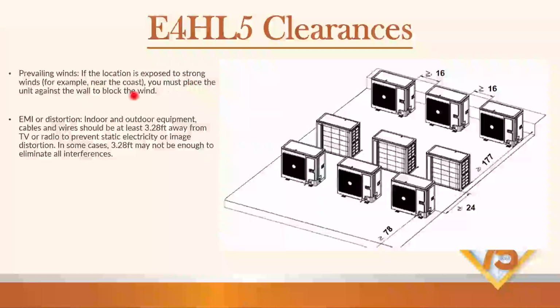Prevailing winds, if the location is exposed to strong winds, you must place the unit against the wall to block the wind. Yeah, you want to keep that in mind because these outdoor fans don't have much torque to them. So they will spin backwards if it gets hit with high winds. EMI or distortion, indoor and outdoor equipment, cable and wire should be at least 3.2 feet away from TV or radio to prevent static electricity or image distortion. That's saying that we've had some weird things happen where radio towers will interfere with comms and our line voltage and whatnot. So keep that in mind.